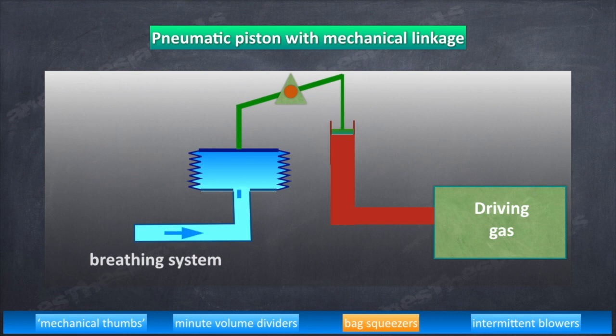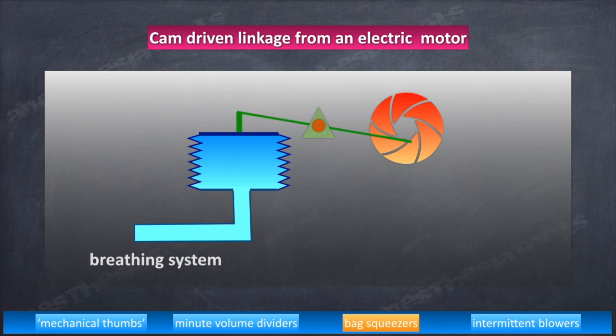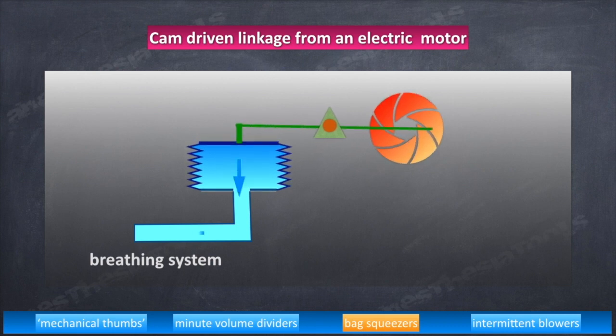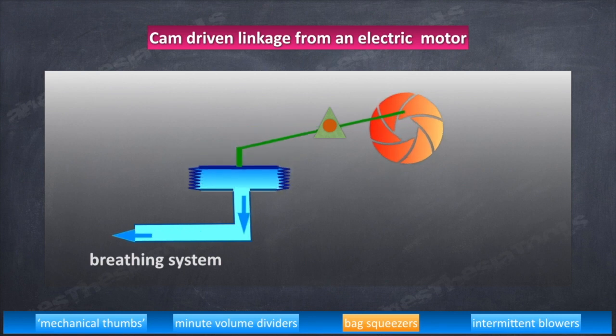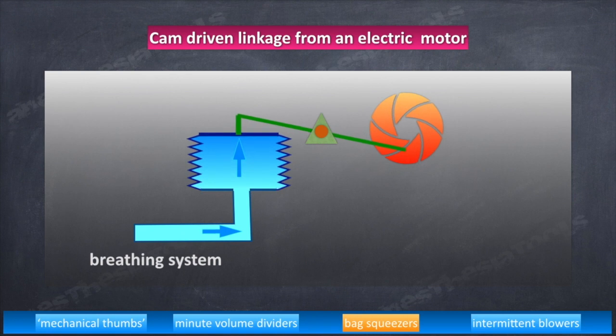Now into exhalation phase. The bellows may also be squeezed mechanically by means of a motor and suitable gears and levers. The movement of the cam produces a sinusoidal inspiratory pressure rise. In the expiratory phase, the bellows may be re-expanded by the pull of the piston. In some models, the piston rod is decoupled during exhalation phase. It is called as lost motion drive using springs. This is no longer a common method.